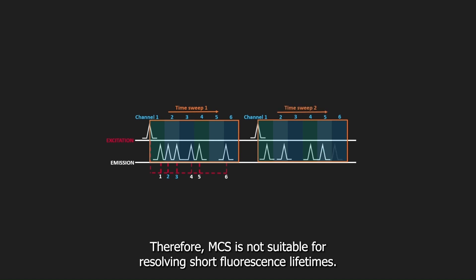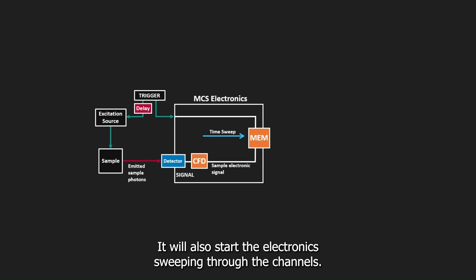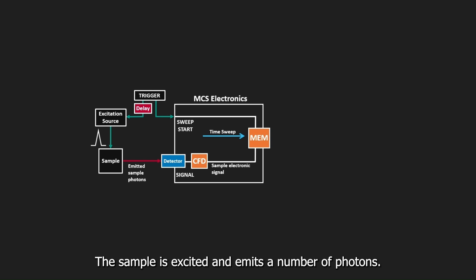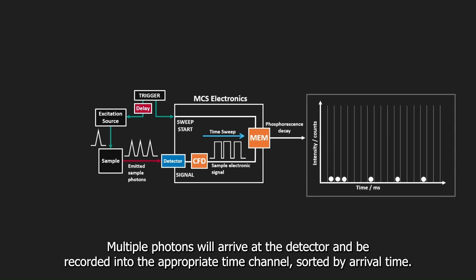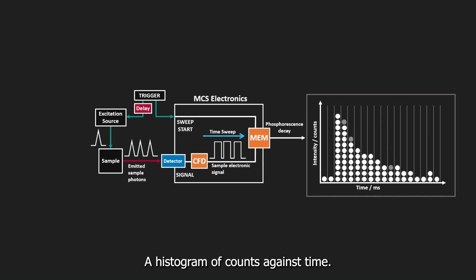All photons arriving within a channel will be grouped together. Therefore, MCS is not suitable for resolving short fluorescence lifetimes. The computer triggers the excitation source — a pulsed laser or flash lamp — and will also start the electronics sweeping through the channels. The sample is excited and emits a number of photons. Multiple photons will arrive at the detector and be recorded into the appropriate time channel, sorted by arrival time. These counts are built up into the phosphorescence decay curve, a histogram of counts against time.